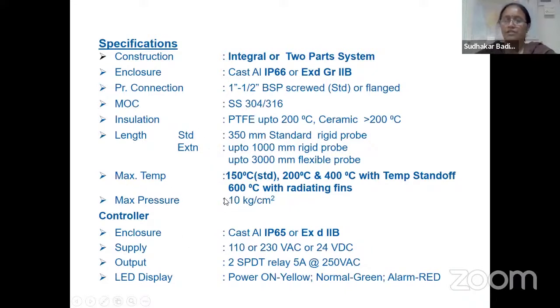Maximum temperature is up to 600 degrees Celsius with radiating fins. The enclosure of the controller is also available as IP65 or Ex d IIB. The supply will be 110 or 230 volt AC or 24 volt DC. The output will be two SPDT relay contacts, which are suitable for 5 ampere 250 volt AC.